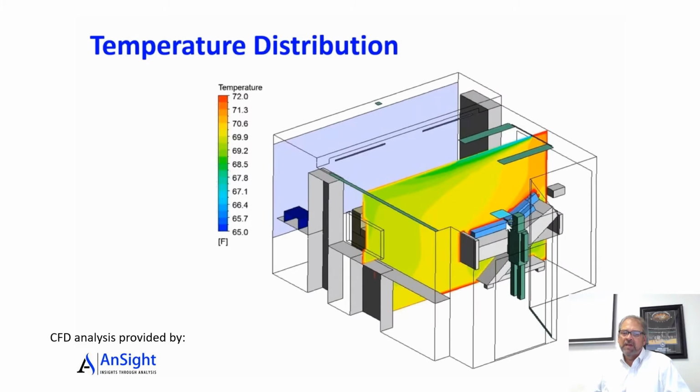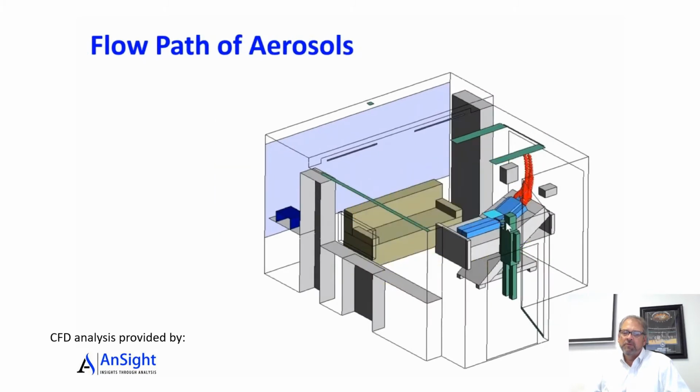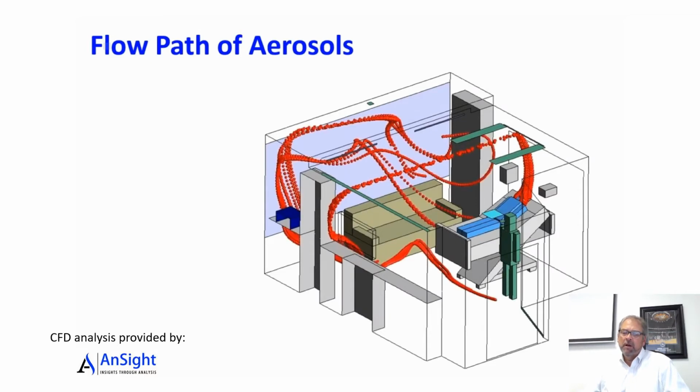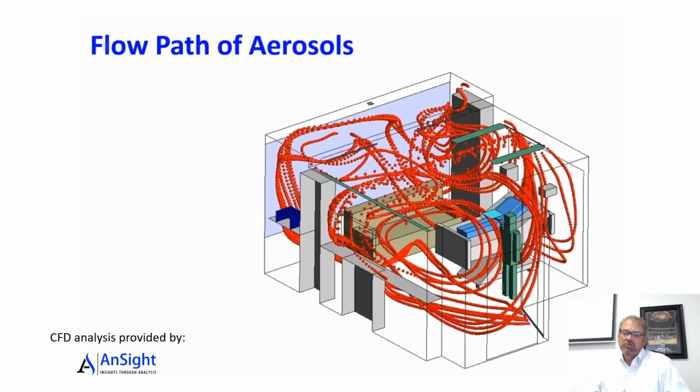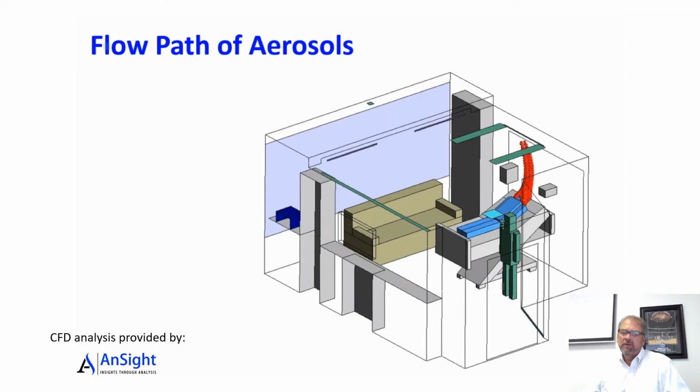Now let's take a look at what's happening to the patient in the bed. You can see that there's a thermal plume created above the patient's head, and the particles that are given off by that patient, which may include viral particles, are distributed amongst the room around the space, just like the rest of the air particles. And essentially, we've ensured that every person in that space gets exposed to whatever particulate that patient is giving off with this type of design.